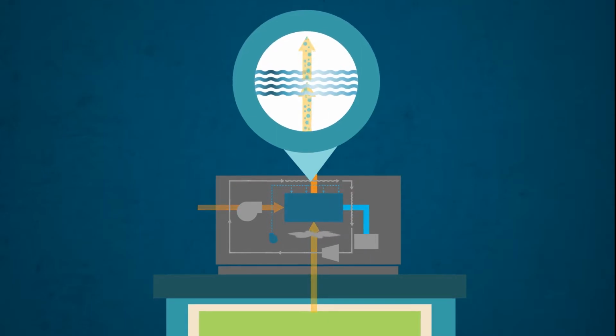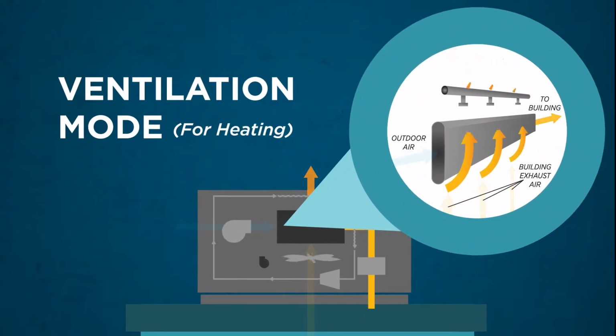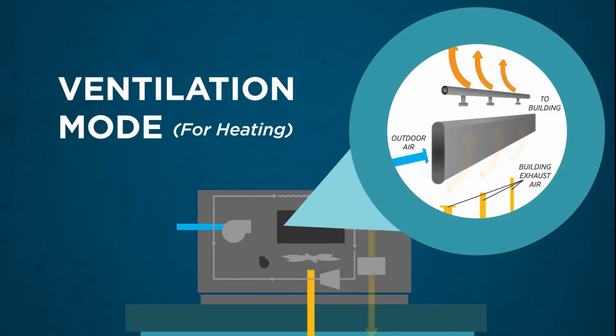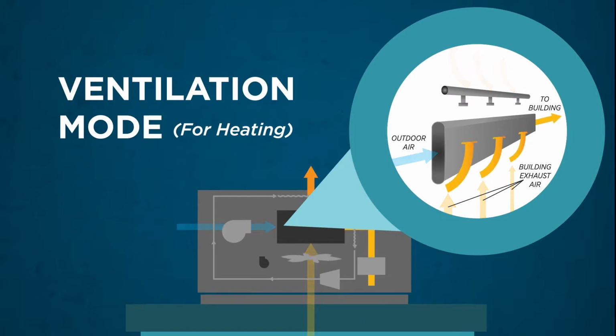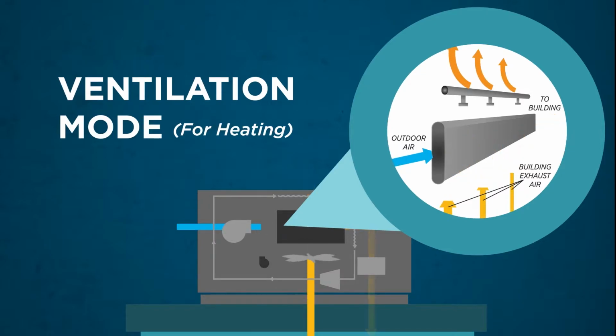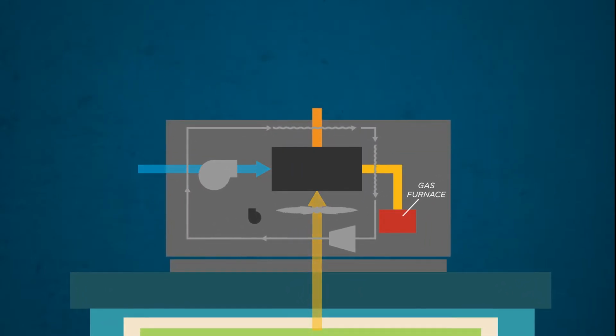In ventilation mode, outdoor air is delivered to the space when the building is occupied. As the outdoor air passes through the supply channels, the air is warmed by transferring heat from the building's exhaust air, which is moving through the exhaust air channels of the heat exchanger. This process provides ventilation to the building while efficiently maintaining the indoor temperature. This heat recovery process contributes significantly to the EPX's annual energy savings. When additional heating is needed, the gas furnace turns on.